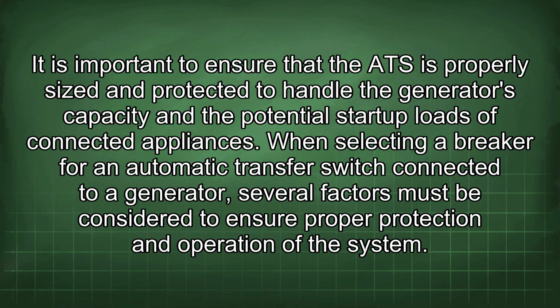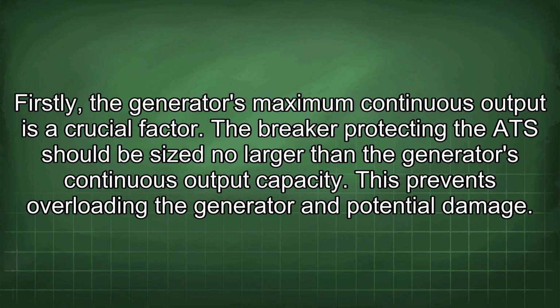When selecting a breaker for an automatic transfer switch connected to a generator, several factors must be considered to ensure proper protection and operation of the system. Firstly, the generator's maximum continuous output is a crucial factor. The breaker protecting the ATS should be sized no larger than the generator's continuous output capacity. This prevents overloading the generator and potential damage.